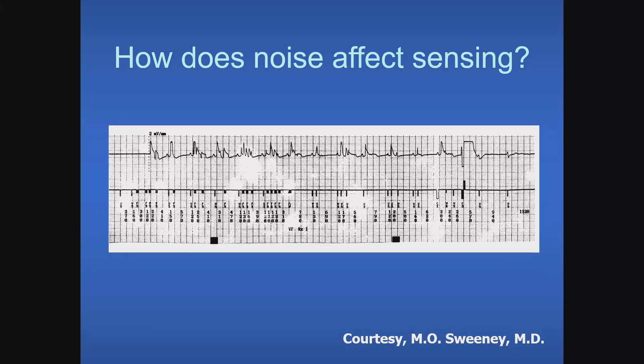This is a patient that was having electrocautery-induced noise, and here you have very rapid sensing in the marker channel that does not reflect these slow beats that are the true heartbeat that the patient is having. And here you can see that the device actually did charge up the capacitors and deliver a shock to the patient in sinus rhythm. Now, this is very painful for the patient if it does happen. It's also dangerous because it could initiate an arrhythmia in a situation where there was not an arrhythmia to begin with. And in a situation where the lead is fractured, it could initiate an arrhythmia that the device is incapable of resolving on its own.